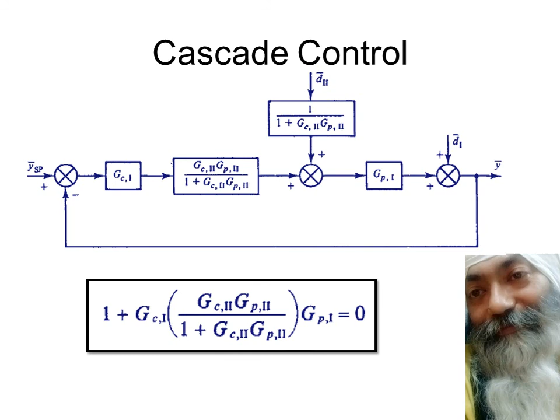All those things I'm not going to repeat once again over here in the cascade control. Let's now try to summarize the things as we will be seeing in the next slide. The first thing we see is that the two controllers of the cascade controller are normal PI or PID controllers, but we normally use only a proportional controller for the secondary loop. We can add a little bit of integral action, but we don't add much. We can afford a little bit of offset, but we cannot afford overshoots.